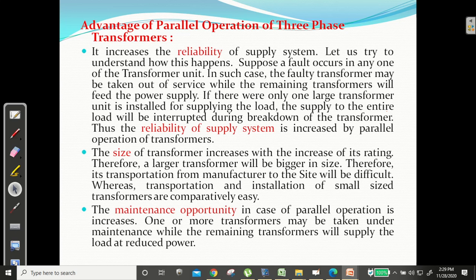The third advantage is maintenance opportunity. Suppose transformers are in parallel - if you want to maintain one, just disconnect it from supply and maintain it, while supplying power through the remaining transformers. But if there was only one transformer, you can't maintain it without stopping supply to consumers. So these are the advantages of parallel operation.